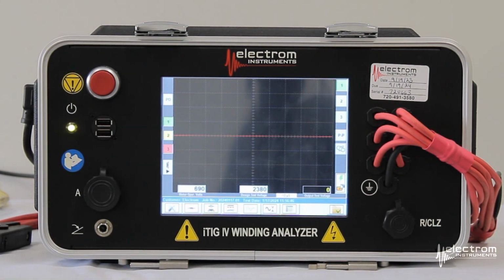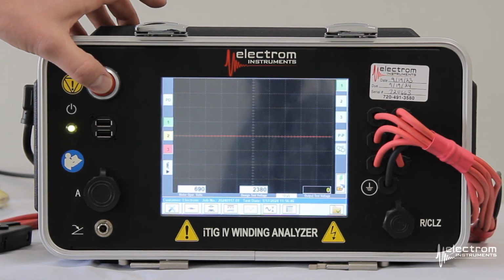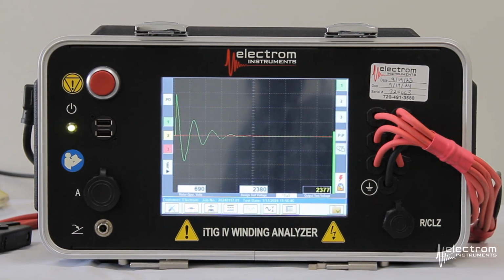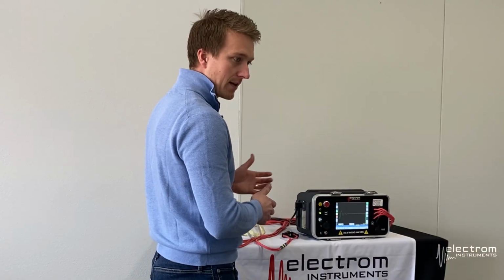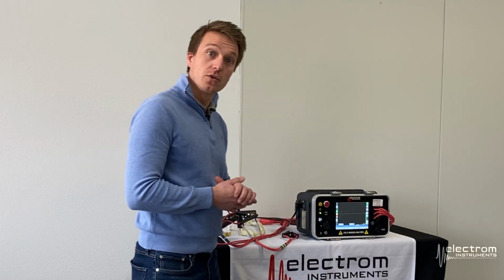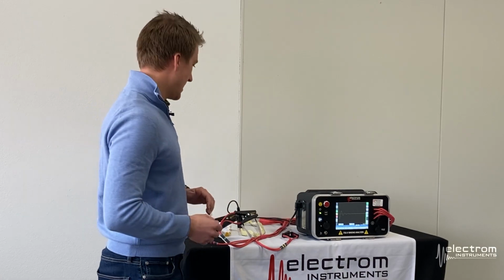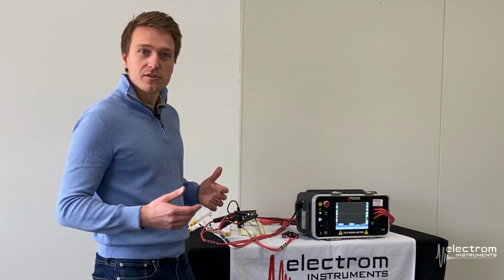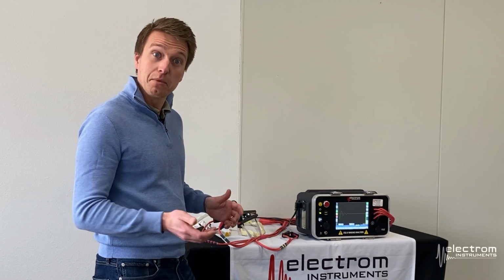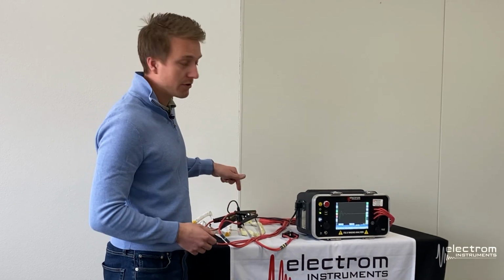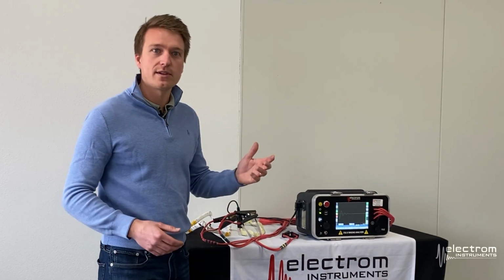Make sure we don't touch the coil during the testing. Press the red button to run the first test. The instrument will then set the voltage scale and time sweep and then drive in the pulse train at our design test voltage. All right, so now we have the test done on the first coil in the coil batch. We don't necessarily know if this coil is a good coil or a bad coil. If you have suspicions of good versus bad, then pick a good one, because we're going to use this first test as the reference as we go through the rest of the coil set.